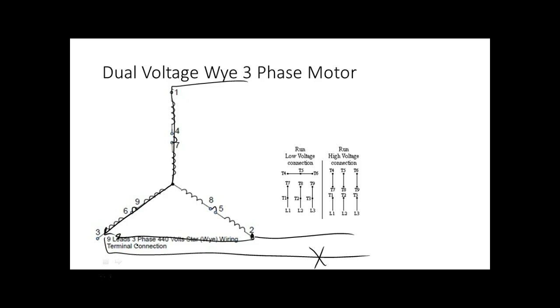What you're doing is measuring through the other phases that still have voltage on them. You're hooking a load, the meter, onto that path, and since the meter has such high resistance, it's not going to load it down.